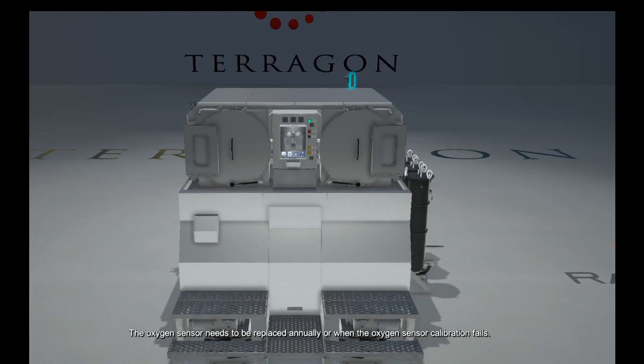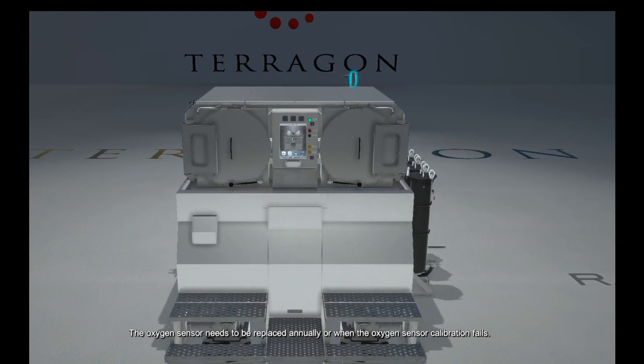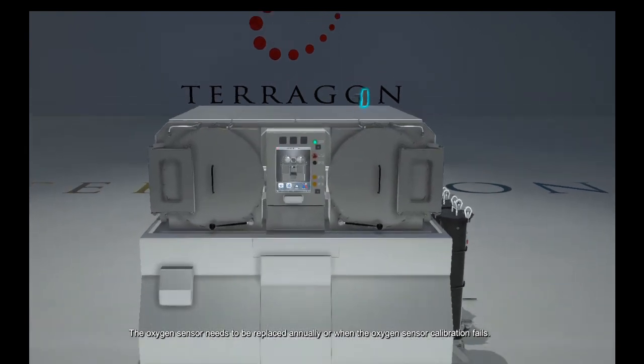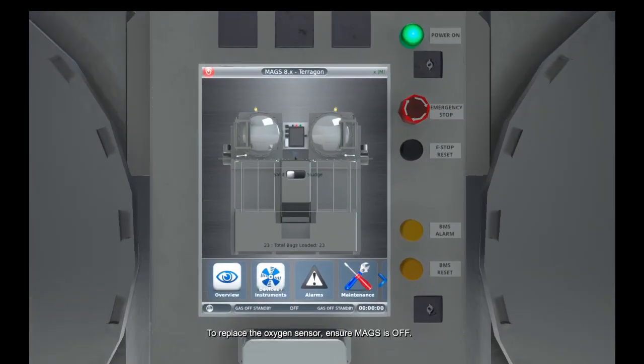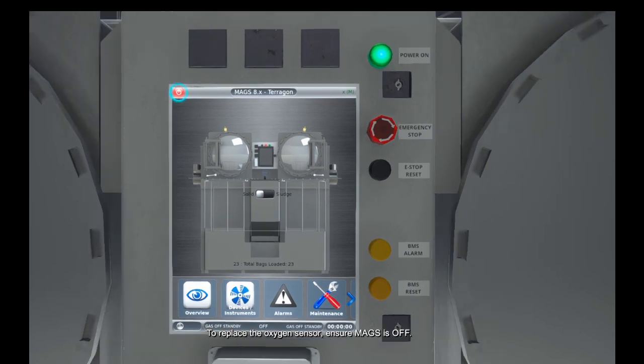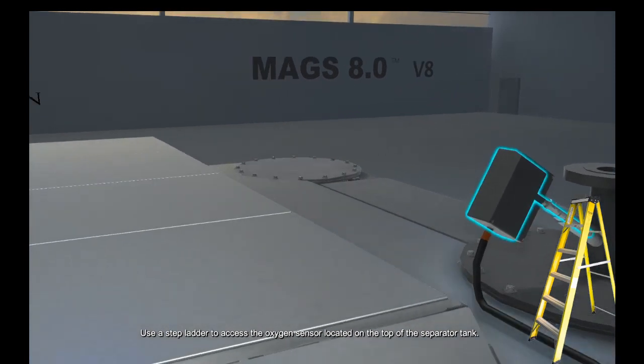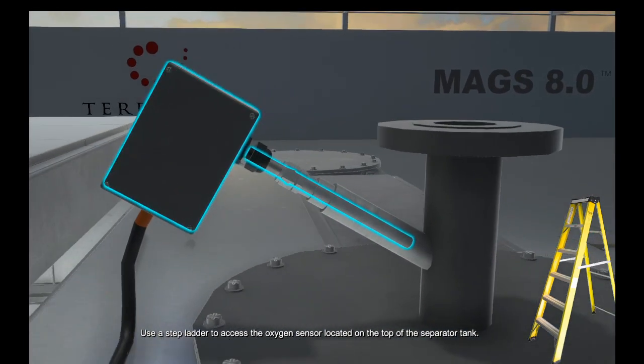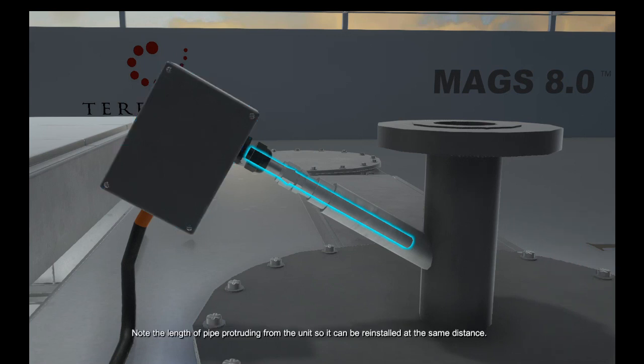The oxygen sensor needs to be replaced annually or when the oxygen sensor calibration fails. To replace the oxygen sensor, ensure MAGS is off. Use a step ladder to access the oxygen sensor located on top of the separator tank. Note the length of pipe protruding from the unit so it can be reinstalled at the same distance.